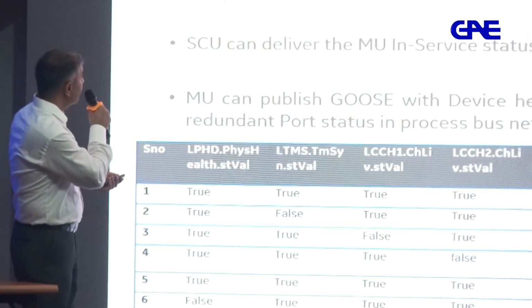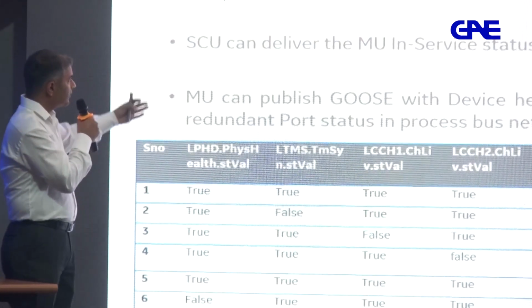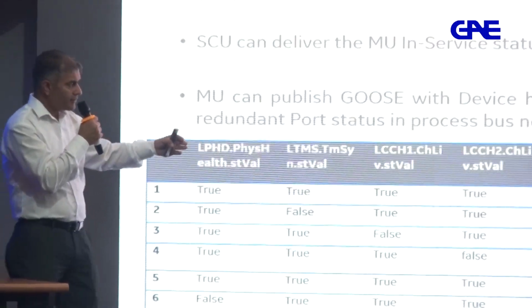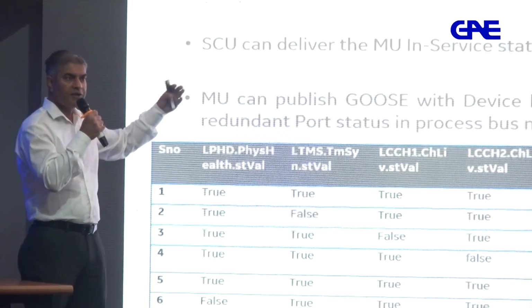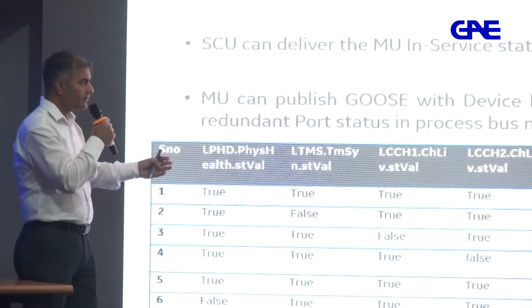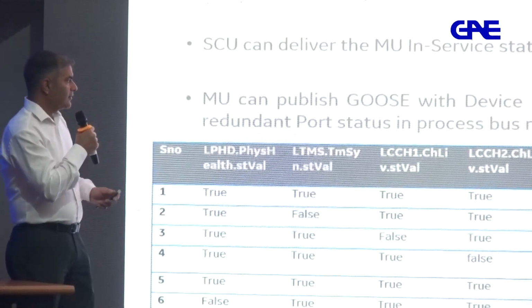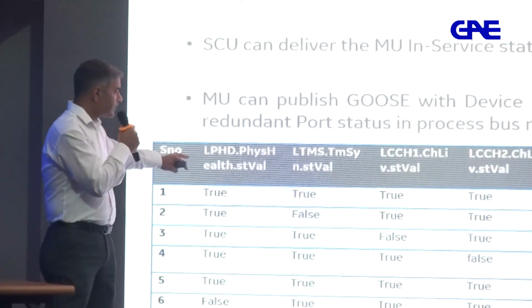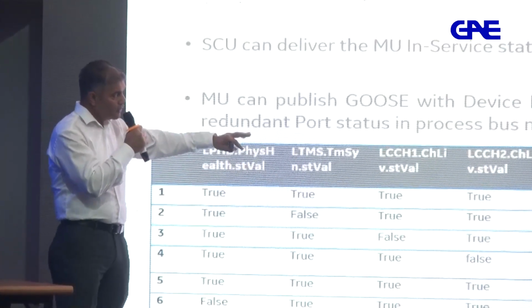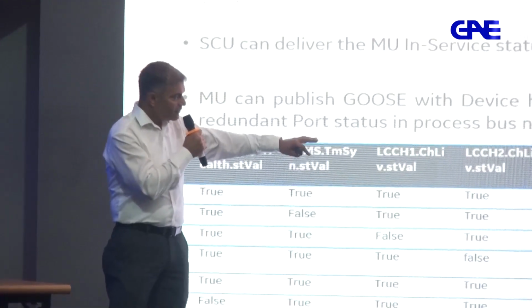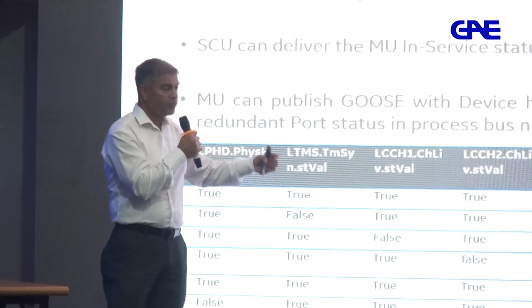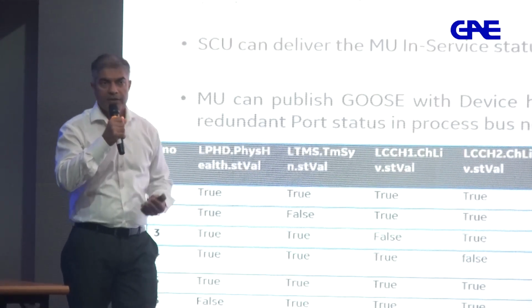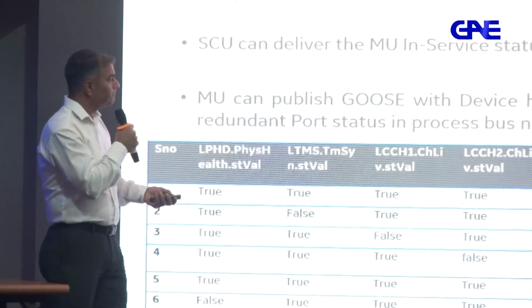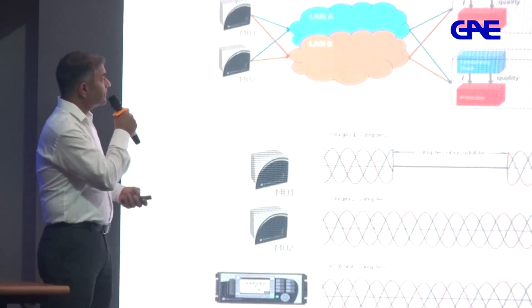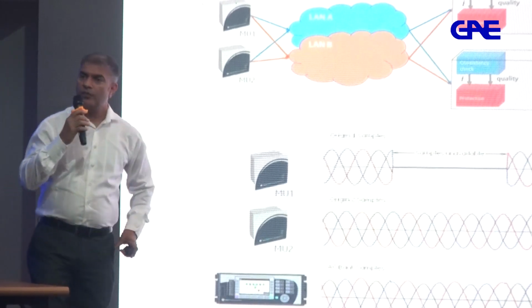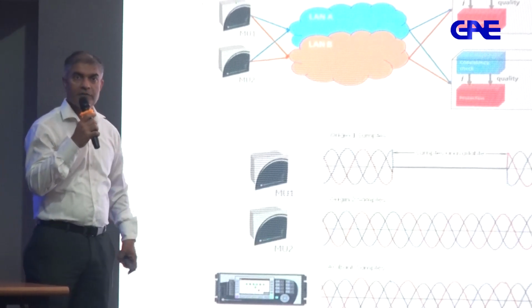Okay, and some of the improvements. This is how we monitor the MU health at HMI when it is not connected to station bus. So this was one example. At HMI level, you can see that we can monitor different logical nodes and how we display them in HMI. So all that time sync fail or single device link failure, all those things we can monitor in HMI, but it needs additional engineering. Right, then some of the possibilities. We can do some innovative things.